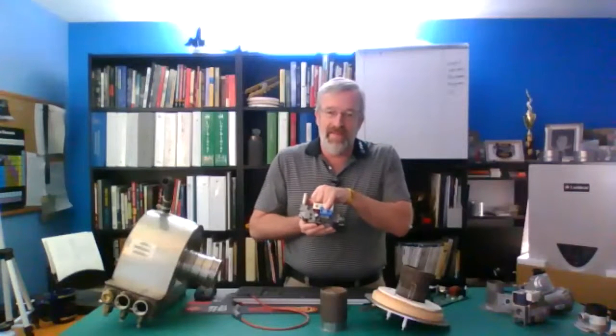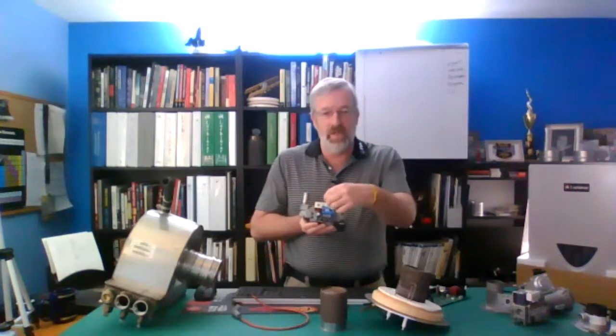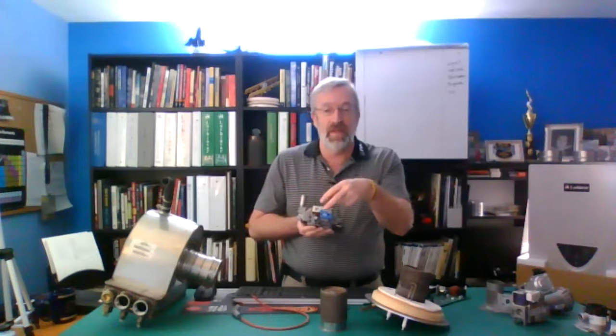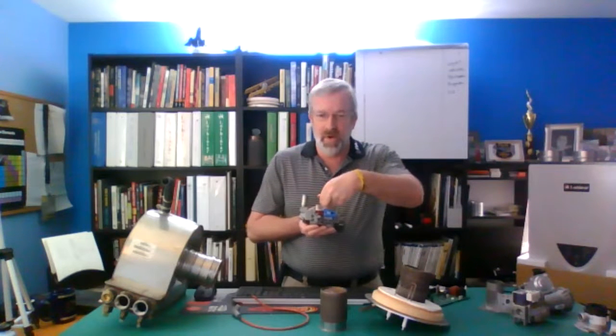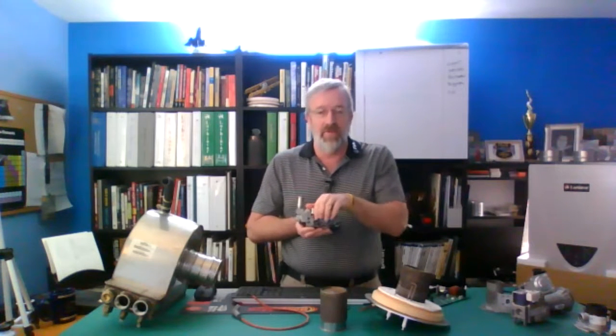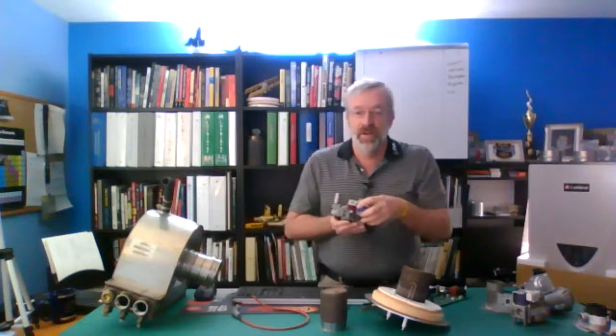How do we troubleshoot that? Well, on a call for heat, our control board sends 24 volts out here to our gas valve. So we want to make sure that we're receiving it here. Now, one of the things to be careful of is these have a pretty small set of pins in there. And a lot of times people take that Molex plug out and insert their multimeter probes into those pins. We really want to avoid that and try to take the reading from the outside of the Molex, reaching in. Otherwise, you can stretch out those pins. And maybe this wasn't your issue, but in troubleshooting, you then damaged the Molex plug connector. So make sure you're not stretching out those pins.